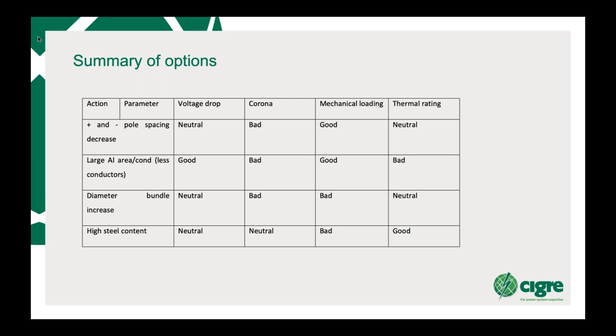If your bundle diameter increases, it doesn't have any effect on the volt drop. It's bad for corona, bad for mechanical, and neutral for thermal. So you wouldn't do that for DC lines. If you're looking at a bundle design for DC, you would put them just in the limit of subconductor movement, as I said, about 15 diameters. High steel content, again, is not really too much of an issue for this.